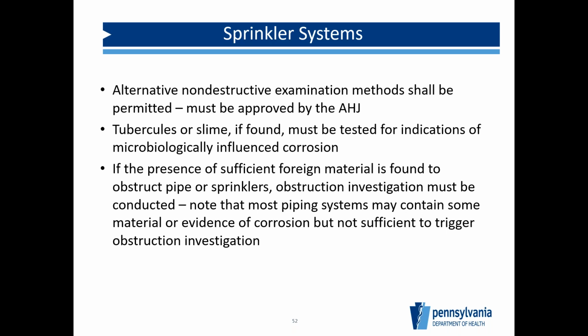So this 5-year test, the goal is to have them do the inspection. If the sprinkler pipes look good, then we'll come back in 5 years. If not, and if we do find a bunch of material in the pipes that would obstruct the sprinkler system from working, then we have to do the more requirements that are listed under obstruction investigation. So if you have the test done and they say, hey, we have so much material in here, you have to do obstruction investigation, then that's something you can talk to the field office about and see what that means in NFPA 25. But it's more of an investigation to make sure that foreign material isn't going to stop your sprinkler system from working when you need it the most.